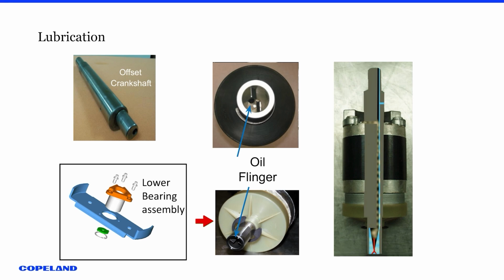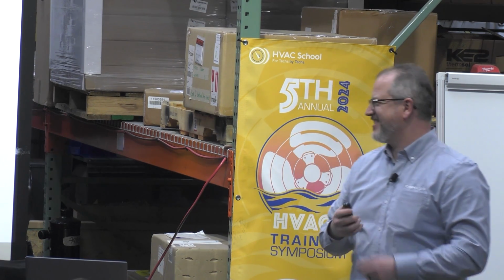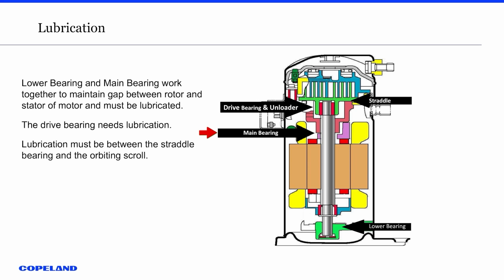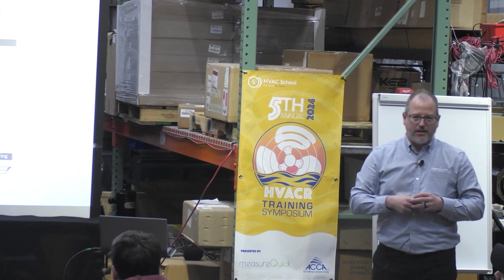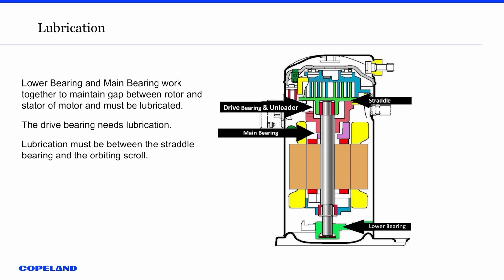Yes? Inside of the bottom of the shaft, I believe there are 2 little feet that scoop the oil up. Exactly. Yep, and I'll show a little picture of that. The little flingers. Yeah, you should be up here teaching. That's awesome. So, a lower bearing, main bearing, and then drive bearing with this straddle on top. Okay? So all those surfaces need to be lubricated inside the compressor at all times. Again, anytime we have metal on metal, we need to lubricate that, right? And we need to keep that temperature down. Otherwise, we're going to lose our lubrication process.